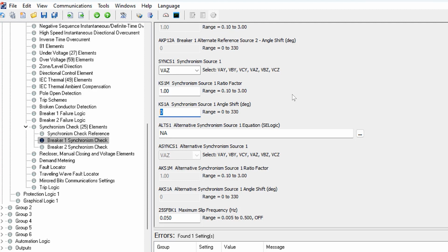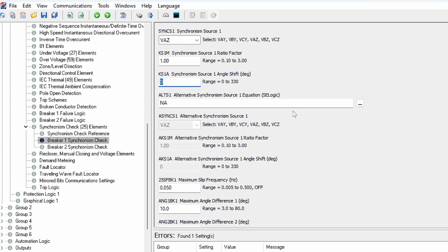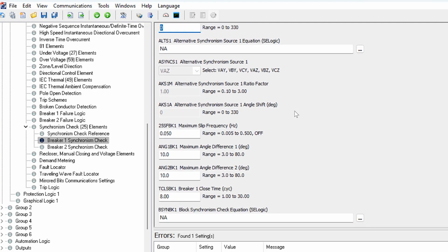And just as a side note, this is why I said earlier that to keep things simple, you could wire the same phase from both sides of the breaker. All right, so we can leave those at default, 1.0 and 0. And let's scroll down here to the rest of the settings. So here we have a setting that's called the slip frequency or the maximum slip frequency allowed. What slip frequency means is the difference in the frequencies between both sides of the breaker. So one side might have a different frequency than the other, which means that the phase angle difference is not going to be static. They're going to be changing with time.